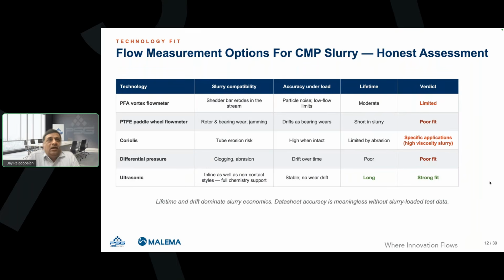Coriolis technology is extremely ideal for high viscosity fluids, especially slurries such as diamond slurry, which is a highly viscous fluid, in which case Coriolis is perhaps the only fit. For other applications, because of cost, people prefer an ultrasonic over Coriolis. But wherever there are high viscosity applications, Coriolis is a better fit. Differential pressure, while it can be suitable for clean fluids, is definitely not suitable for CMP slurry because you're crossing an obstruction in the flow path, and that can lead to clogging or abrasion and drift over time. So that would not be a fit.